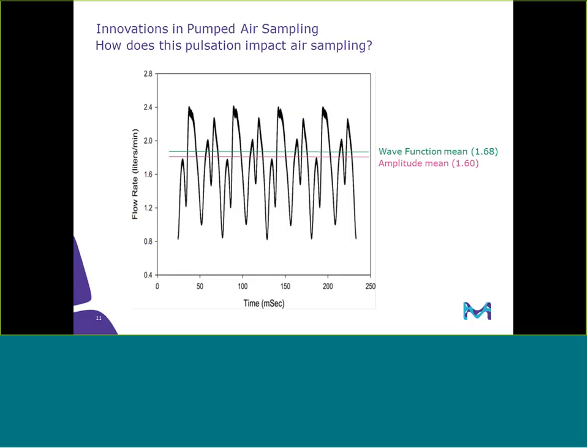So what do we do if you don't have an ideal waveform for the pump that you have? In this example, depending on how flow rate is calculated, you can see that there are two different flow rates. There's an amplitude flow rate, or the wave function mean, and that's already a 5% difference in that value. So are we giving away 5% in accuracy right off the bat?